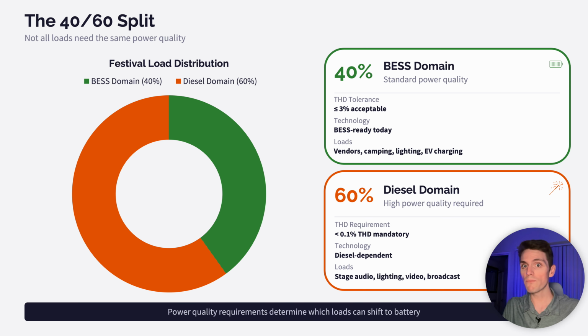Analysis reveals that 40% of total festival load requires only standard commercial grade power quality, 3% THD or less, which today's inverters deliver just fine. Over 60% of the load, the audio, stage lighting, video, and broadcast, needs the sub 0.1% THD that diesel naturally offers. The power quality requirements determine exactly which loads can shift to the battery.